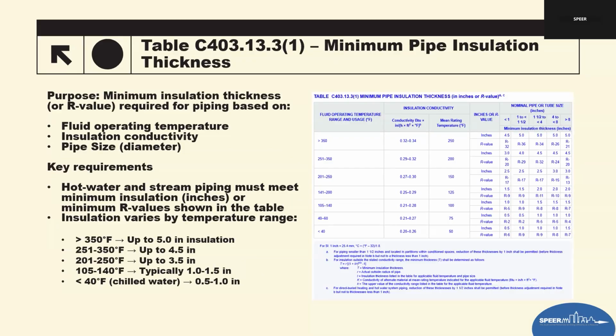Not that the energy code is getting into more of the water stuff, but it does talk heavily about minimum pipe insulation thickness. So as you see here in the table, 403.13.3 (1) provides requirements for minimum pipe insulation thickness for mechanical systems in commercial buildings. It covers everything from the chilled water lines to the high temperature steam. It basically dictates how much insulation is necessary to limit heat loss or gain and improve system efficiency.